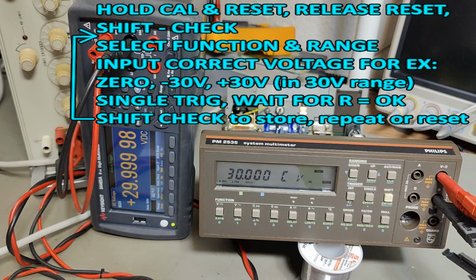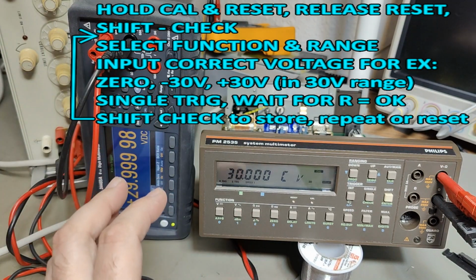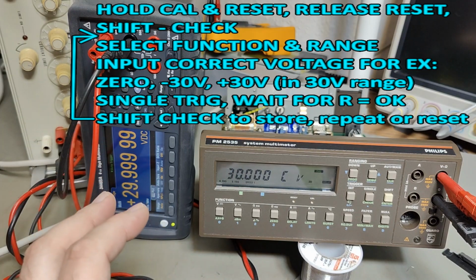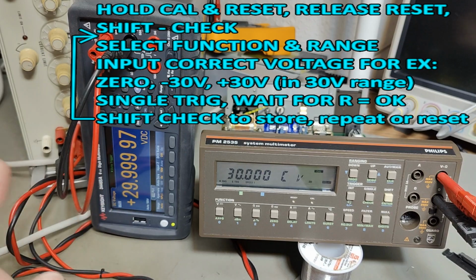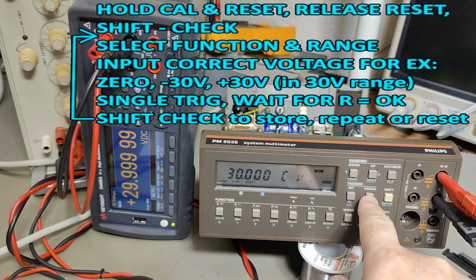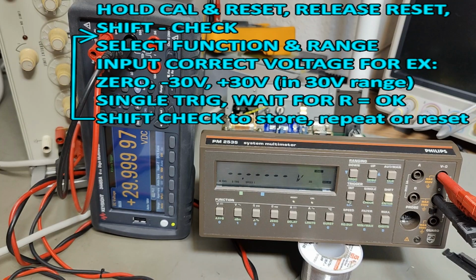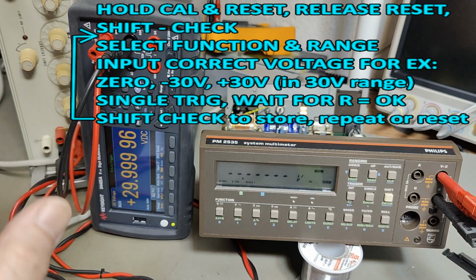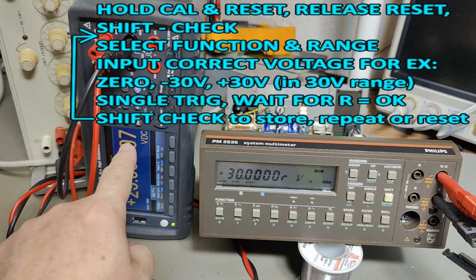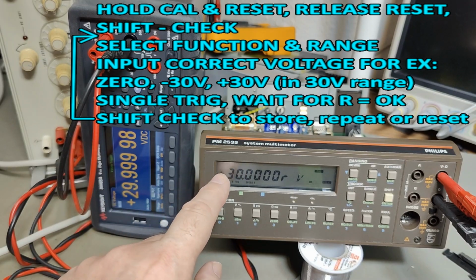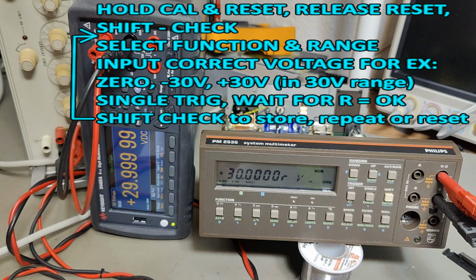You got three options in this 30 volt range. You can either input 0, positive 30, or negative 30. It will auto detect which one of the three things you're doing, but at the moment I'm just doing positive. So when you are ready with the positive, then you simply hit single trig. So here is single trig, and then it's gonna perform a lot of average and stuff. Oh, and you can even see that my input is a little bit low now, so I should have adjusted my input to be exactly right. But now it has stored a value that is a little bit too low as the correct input for 30. But you get the point, right?